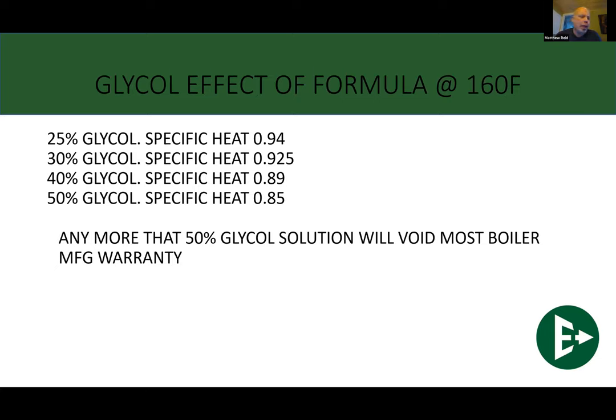When I'm talking about burst protection, that's when your actual pipes can split and rupture and you start losing fluid. Anything less than that, and the solution goes into a kind of slush-type fluid concentration. Now, boilers are fine with slush. They can't do ice. But slush, you can absolutely put through any boiler. So don't be afraid to talk about this glycol percent solution, because instead of oversizing your boiler by 15% by using 50% glycol, maybe you only need to oversize it by 7.5 to 8%, because you know that 30% glycol is actually going to do what you need it to do instead of what you want to think is going to happen. Food for thought.